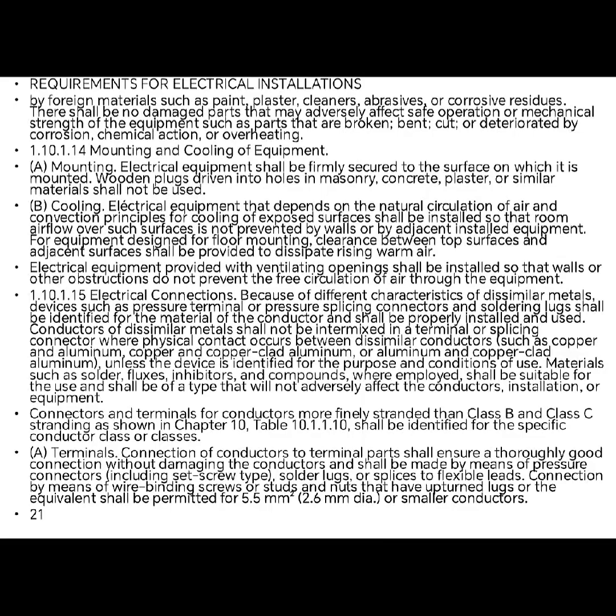freely through the equipment. Number five, electrical connections involving dissimilar metals such as aluminum and copper must avoid direct contact to prevent corrosion. Use suitable intermediate materials or proper splicing devices and terminals for conductors, and ensure solid pressure connections. Terminology: conductors are classified into Class B and Class C based on stranding, as shown in Chapter 10. In short, electrical equipment should be installed securely, kept clean, and given good ventilation.